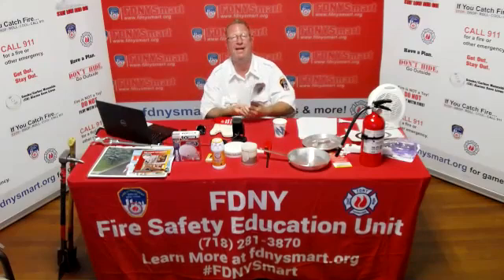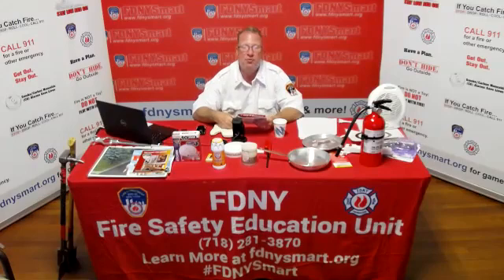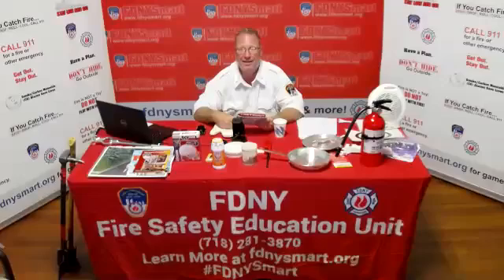Okay, remember the word PASS. The P stands for pulling the pin. The A stands for aiming at the base of the fire. The first S stands for squeezing the handle. And the last S means sweeping side to side in a side to side motion with your back to a way out. Did everybody get that?